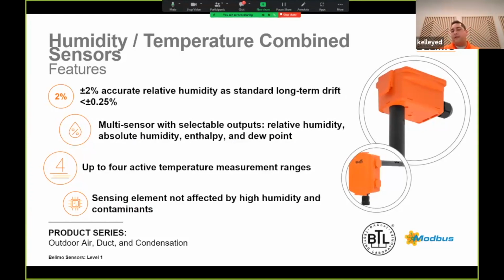One of Belimo's differentiators here in the market, okay, so there's 4 types of humidity that are important to us. We all know relative humidity. There's also absolute humidity, enthalpy, and most importantly today is dew point. So ASHRAE 62.1 is now strongly promoting dew point. Dew point is heavily used in pharma, hospitals, grow farms, and so on. So with all of our Belimo humidity sensors, you just flip a dip switch and it outputs dew point versus relative humidity. And that's the same within our room sensors as well.